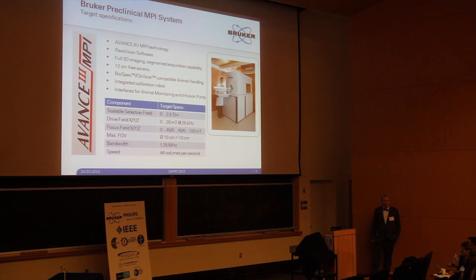The scanner implements full 3D imaging, meaning 3 excitation axes, 3D drive field, in addition with shift or focus field coils to access a large field of view, which is necessary because of a 12 centimeter free access. So the scanner will be suitable for mice, rats, guinea pigs, and even rabbits, which was one of the design goals, going a little further than what's currently done.